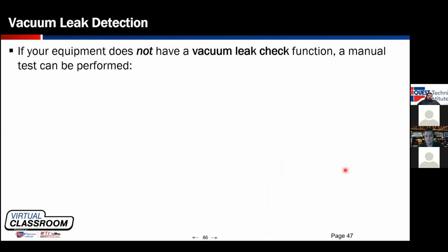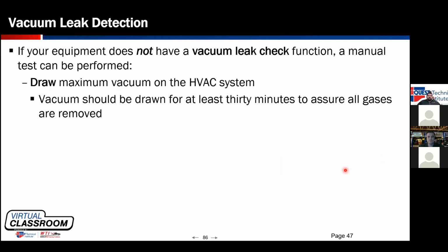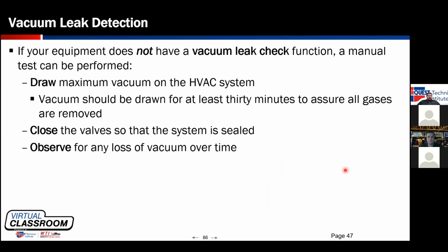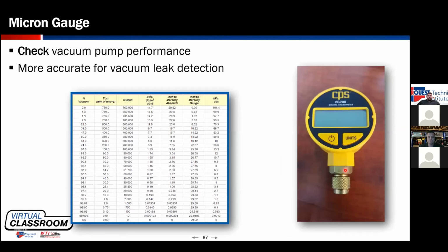If your machine does not do a vacuum decay leak test, you can do a manual test. Pull the system into a vacuum, make sure that the system is in a deep vacuum, that all of the refrigerant and water vapor is boiled out so that it stays in a deep vacuum, isolate the system, and look for loss of vacuum. Now, if you're going to do that test, you really need a micron gauge. Micron gauges are gauges that are designed to measure very, very small amounts of vacuum. A manifold gauge set for air conditioning service is designed to measure a very large range of pressures, and they are not particularly good at measuring small vacuums. So if we want to do a vacuum decay leak test, we really need to be using a micron gauge to do it.